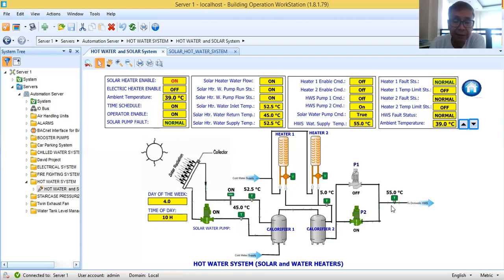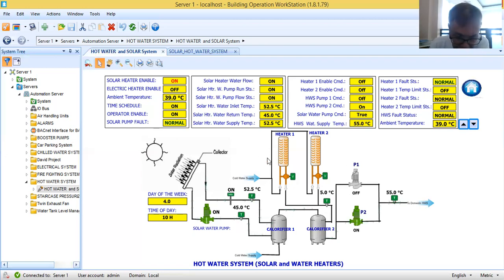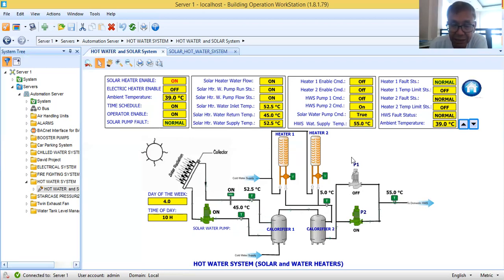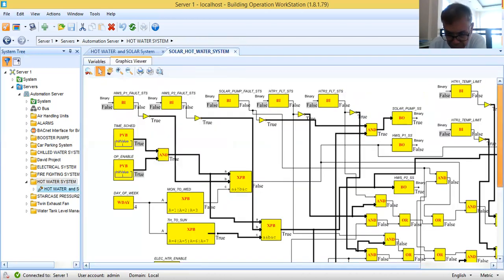In this project I used BACnet MSTP, so if they are also using BACnet MSTP it makes the software integration easy. For those new engineers, there is software integration and there is also hardwired — where you run a physical cable to the control panel to get the control and monitoring points. Since I did the software integration here, what I'm doing now is I have written a simple control logic program.